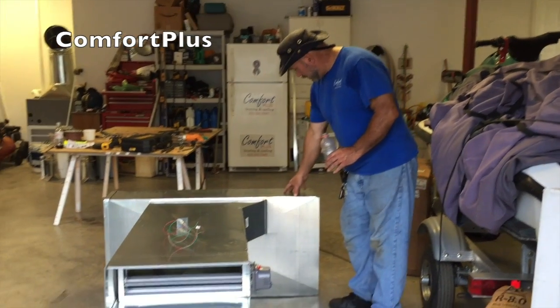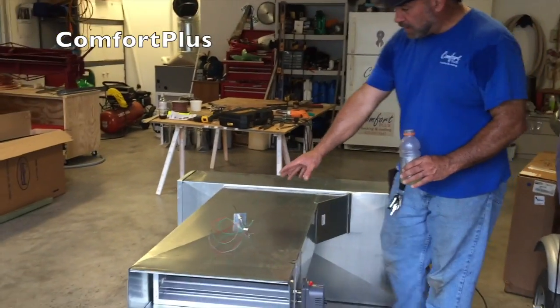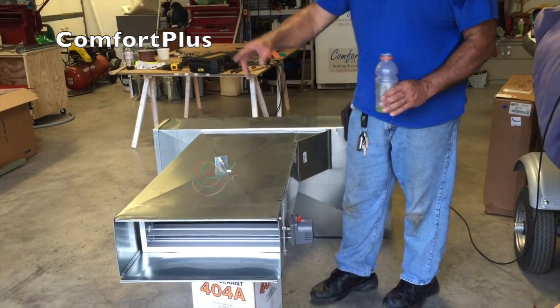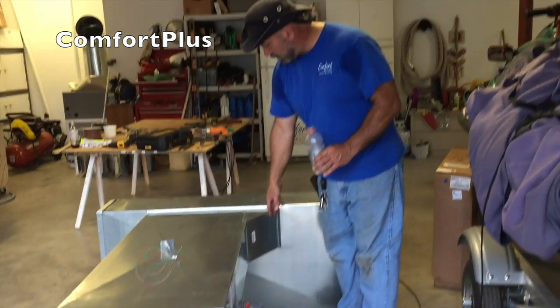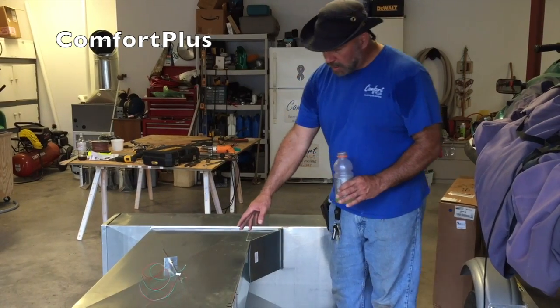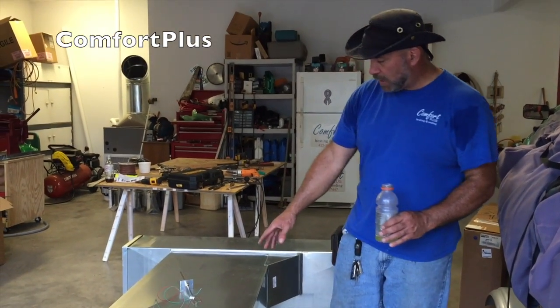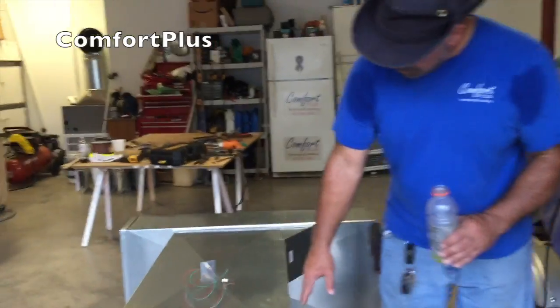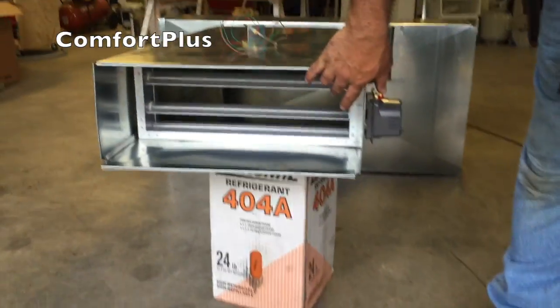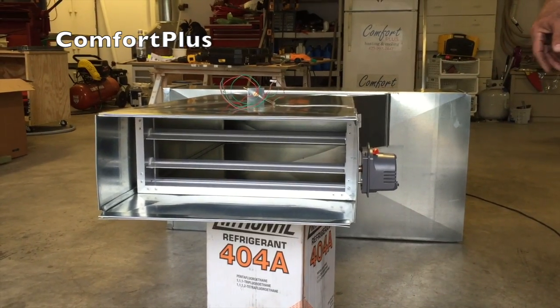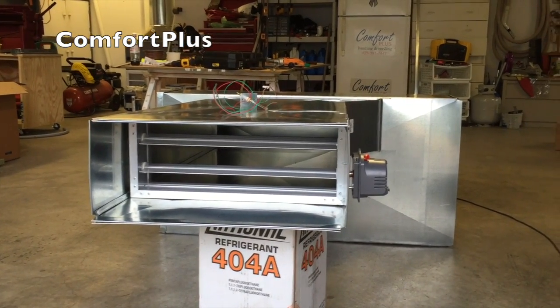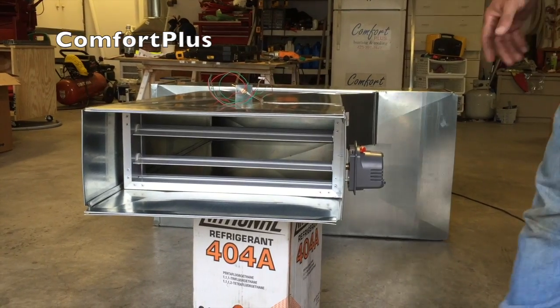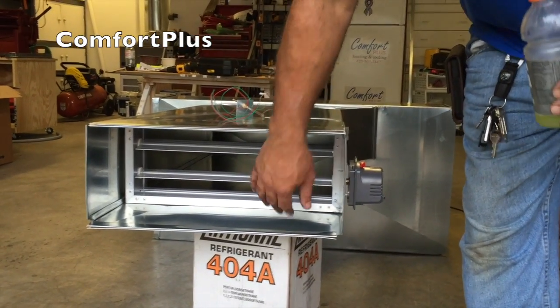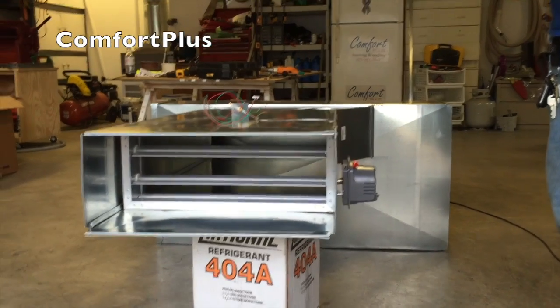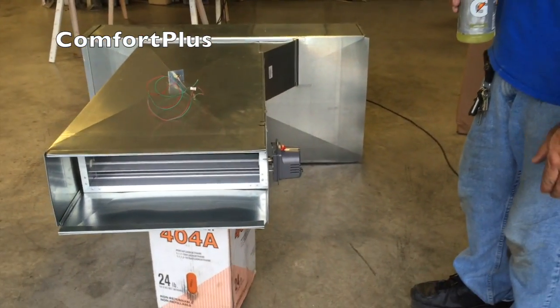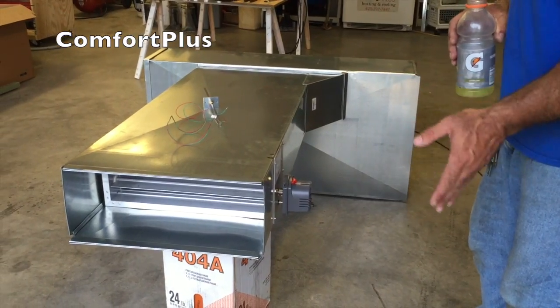Again, what we have is a 10 by 24 trunk duct and two 8 by 20s servicing the individual zones. We flared this out like we talked about. In each one of these 8 by 20 branches, it's going to have a zone damper. That's a Honeywell ZD damper. This particular one is set up right now for spring open and powered shut, which is how I will leave it. That way when a zone is not calling, it will turn it off, otherwise it'll remain open.